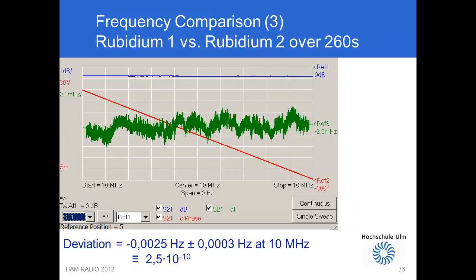Here you see the measurement of the frequency difference between my two Rubidium standards. The red trace is the phase difference as function of time. The slope of the line, being straight, is representing the frequency difference. The green trace is the calculated frequency difference. The noise is due to numerical calculation of the derivative and other noise contributions.